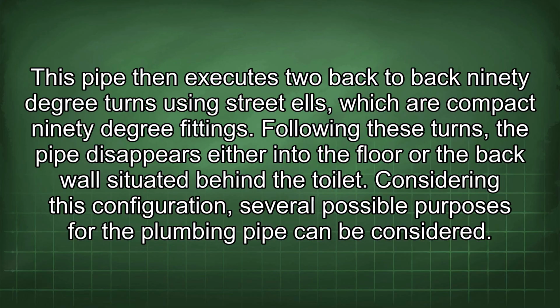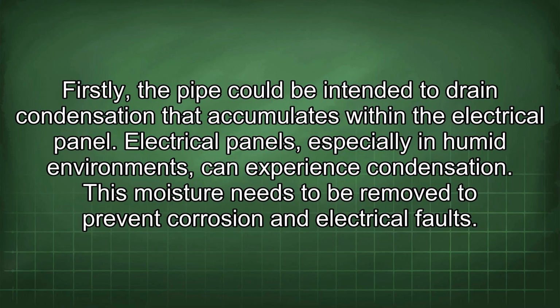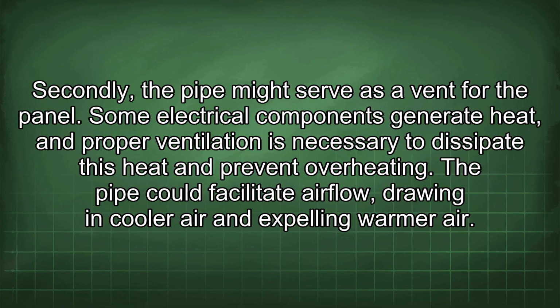Considering this configuration, several possible purposes for the plumbing pipe can be considered. Firstly, the pipe could be intended to drain condensation that accumulates within the electrical panel. Electrical panels, especially in humid environments, can experience condensation. This moisture needs to be removed to prevent corrosion and electrical faults. Secondly, the pipe might serve as a vent for the panel. Some electrical components generate heat, and proper ventilation is necessary to dissipate this heat and prevent overheating. The pipe could facilitate airflow, drawing in cooler air and expelling warmer air.